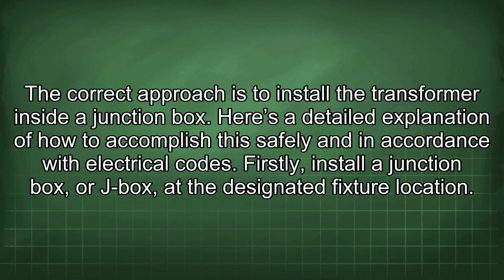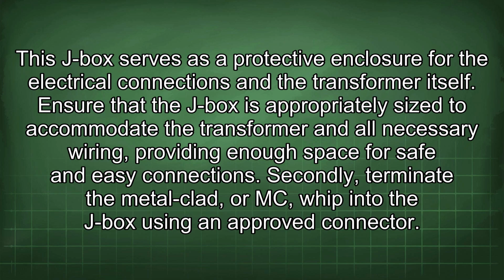Firstly, install a junction box or J-box at the designated fixture location. This J-box serves as a protective enclosure for the electrical connections and the transformer itself. Ensure that the J-box is appropriately sized to accommodate the transformer and all necessary wiring, providing enough space for safe and easy connections. Secondly, terminate the metal-clad, or MC, whip into the J-box using an approved connector.